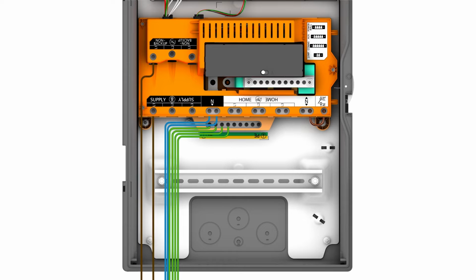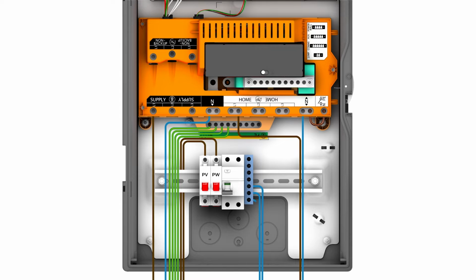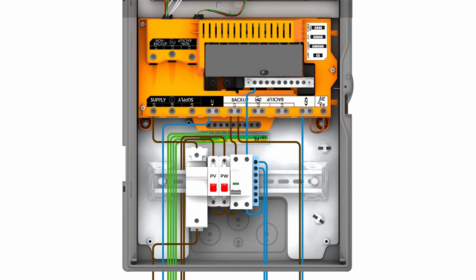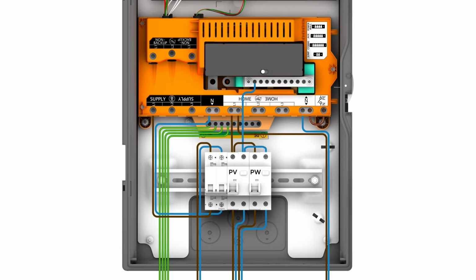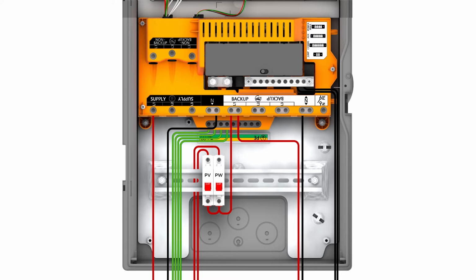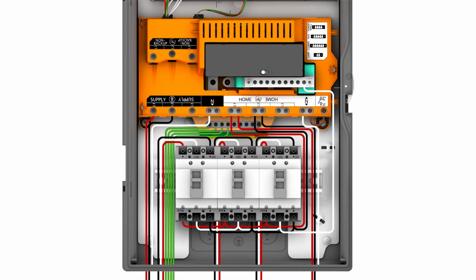Next are the backed up home loads. Connect the home loads to the Line 1 and neutral terminals at the home label. The breakers for Powerwalls and solar inverters are connected to the other set of Line 1 and neutral terminals at the white home label. Use bus bars as needed to supply power to the solar and Powerwall breakers. Here are some diagrams of the same configuration in different regions. In Japan, the configuration is the same except Line 1 and 2 are both used.